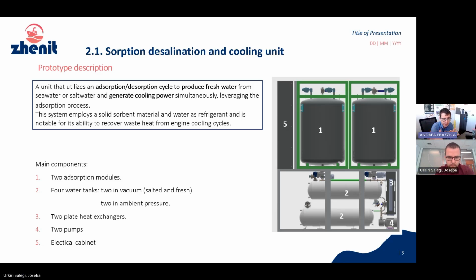The main difference is that in this case we have the evaporator and condenser basically inside the adsorption module itself, so the process is fully active inside that vessel. Then we have the refrigerant, which is water, transferred inside the process through a centrifugal pump, giving us distribution in the liquid phase. The water in liquid phase is much denser than the vapor phase, and the cost is also reduced because of the reduced size of valves, etc.